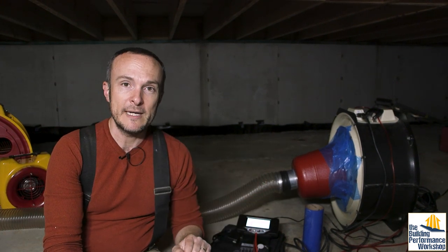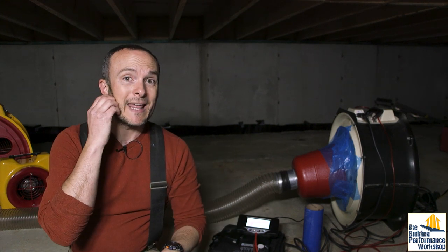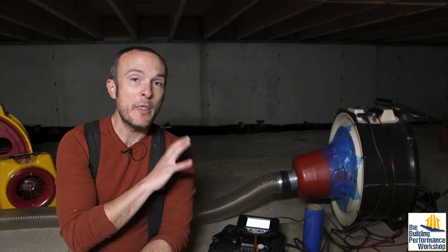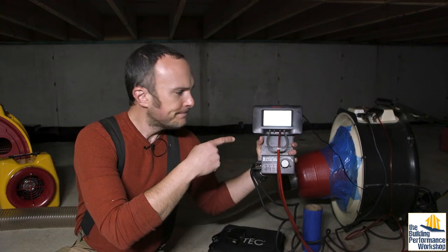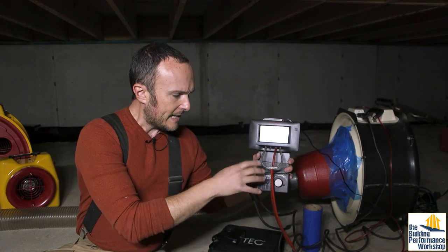I have another blower door device, which is the Model 3 from Energy Conservatory. This one, if you take off the center plate — when it comes to stock, the default set of ring configuration plates comes with A and B. Take off the center plate and you leave the B ring installed, the bell fits perfectly. So we just taped it in place and now I have the Minneapolis manometer, which is the 1000 model, digital, hooked up.